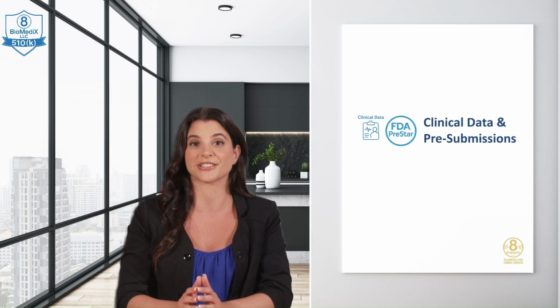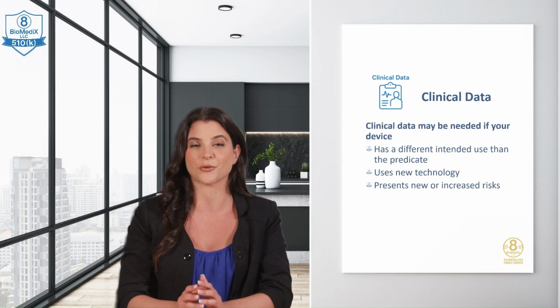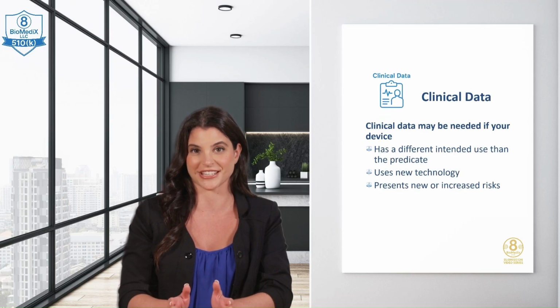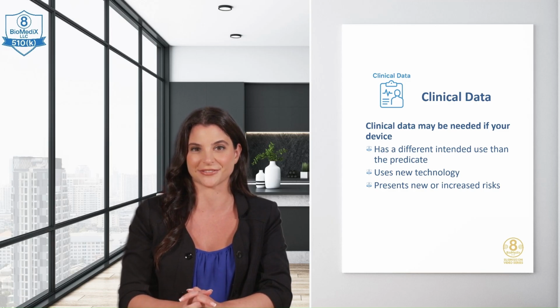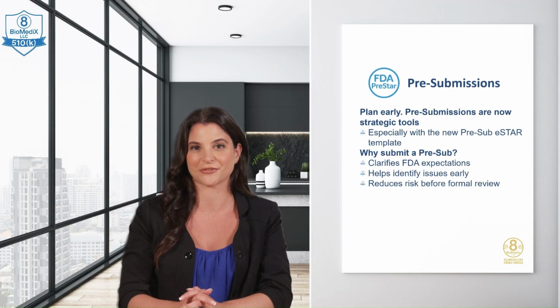Clinical data and pre-submissions. Not all 510K submissions require clinical data, but you may need it if your device introduces new technology, has a different intended use than the predicate, or presents new types of risk. Plan early.